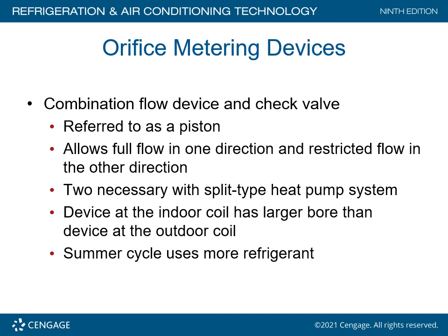Summer cycle will use more refrigerant. Now, I haven't talked about this before, but heat pumps, depending on the design, the type, and the age, are considered critically charged systems. You can't overcharge a heat pump. There's a little bit of forgiveness depending on the piping design. Typically, heat pumps will have an accumulator on the suction line. And the reason is because the chance of having liquid carryover into the compressor is greater, because the refrigerant is not going to be utilized completely in the heating mode.